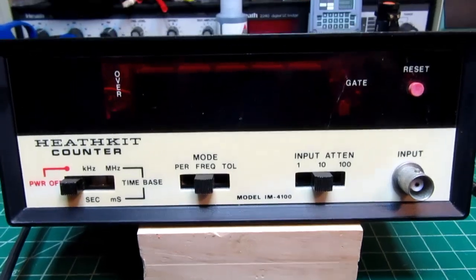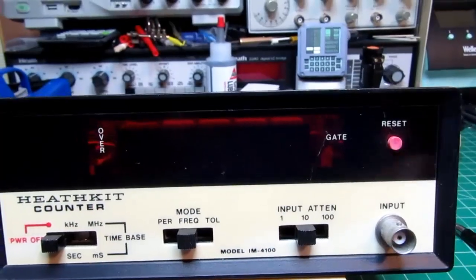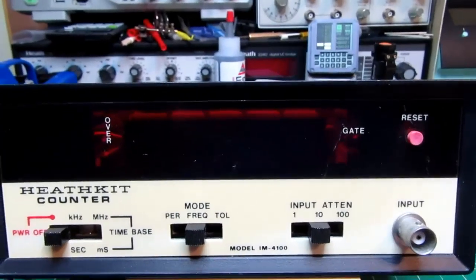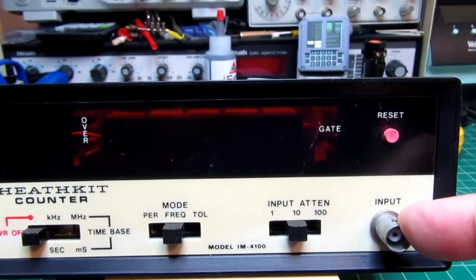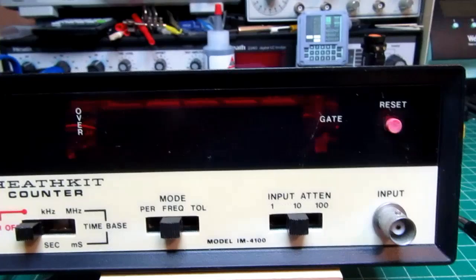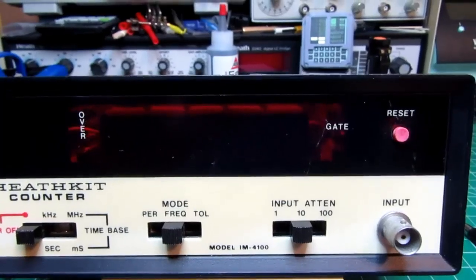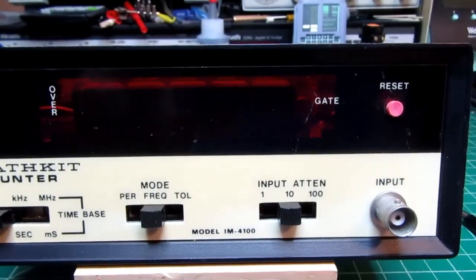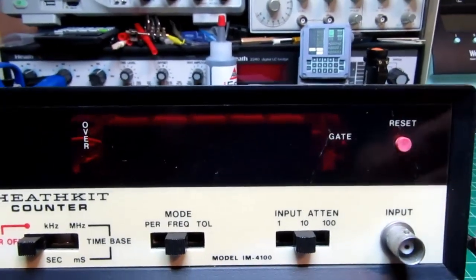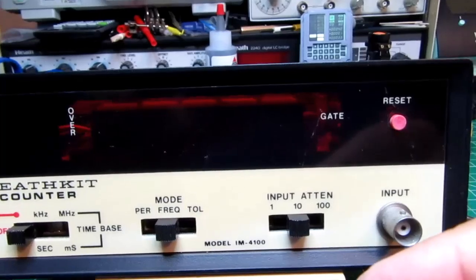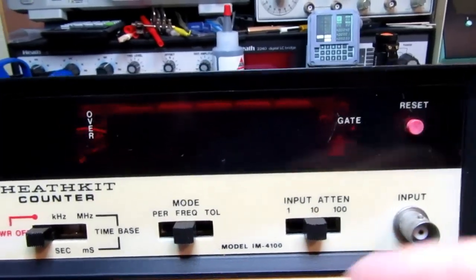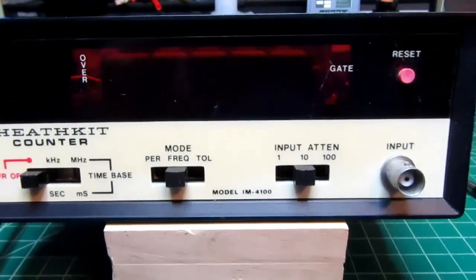The input voltage rating on this, in lower frequencies, all the way up to 100 kilohertz, can tolerate up to 250 volts RMS, beyond which it's not advisable to go. The protection circuitry should protect it, but you could possibly get into a damaged situation, especially if you sustained that for a long period of time. All the way up to 100 kilohertz, you can apply that kind of voltage, or anything down from 250 volts RMS down to very fractional voltages, and it'll still work.